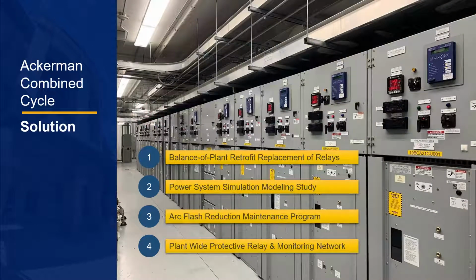Merrick's proposed solution, determined through a Phase 1 analysis, was to perform a balance of plant relay retrofit replacement of all 32 GE Multilin microprocessor protective relays. The relays would be replaced with Schweitzer Engineering Laboratories SEL relays.